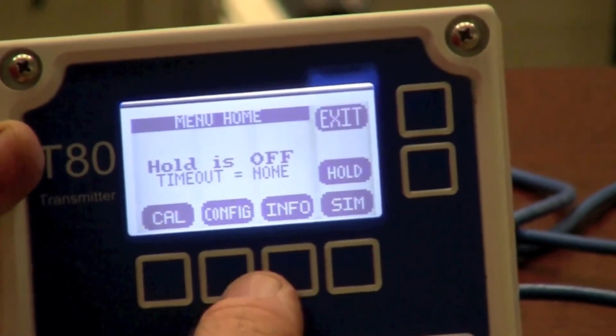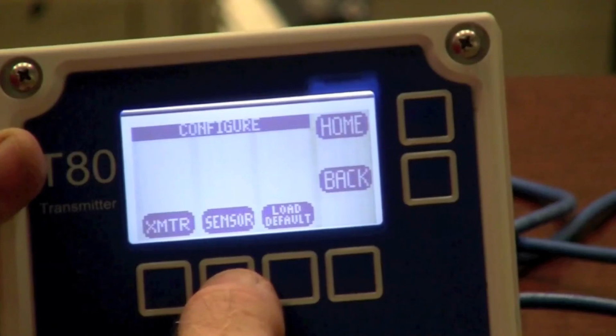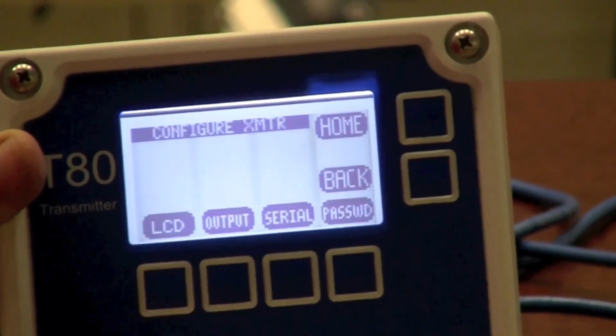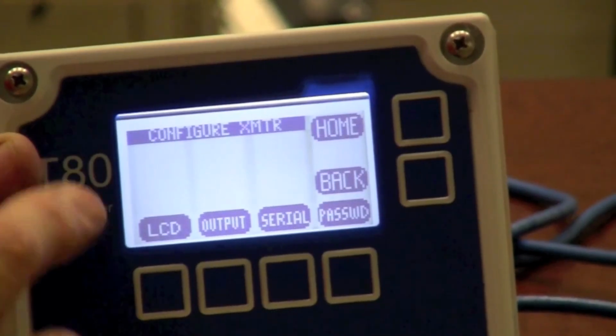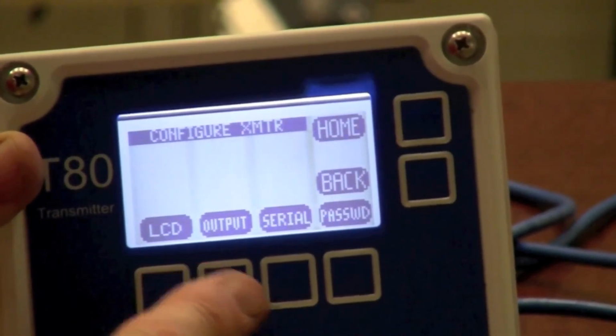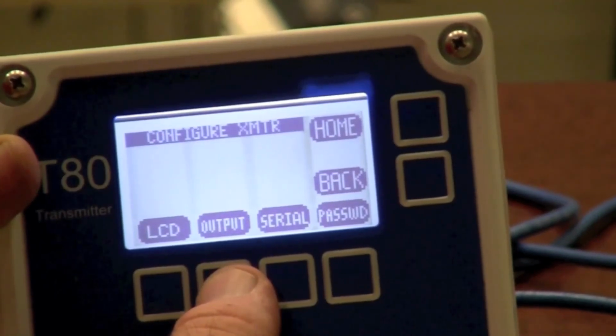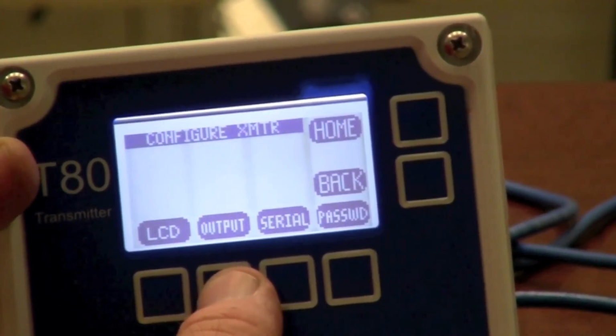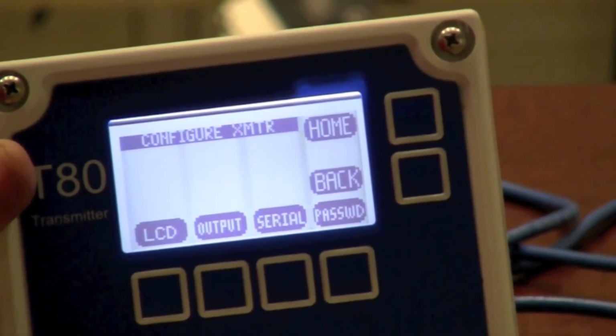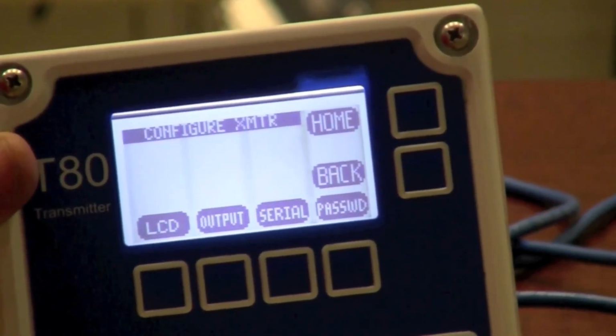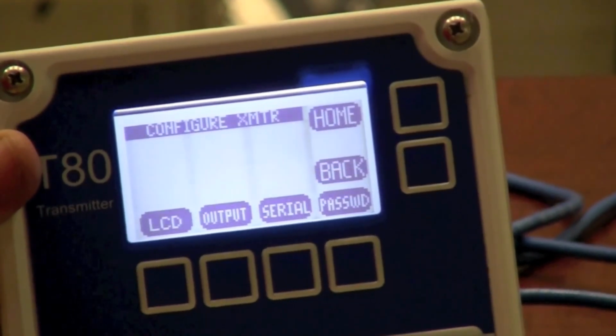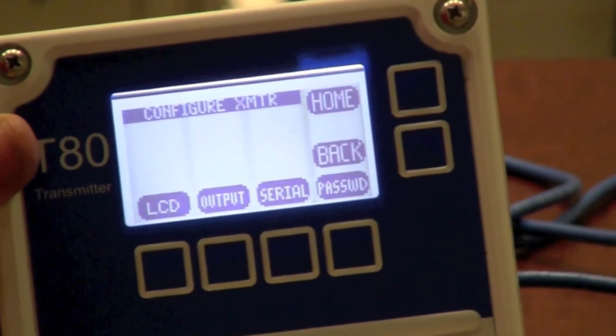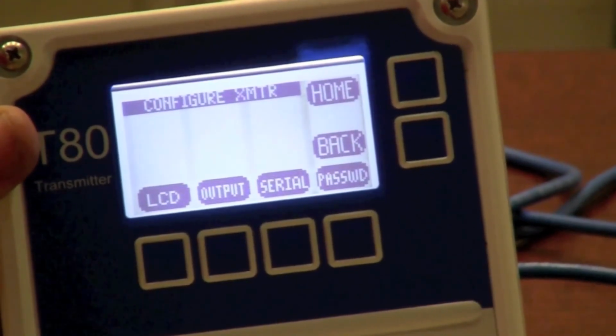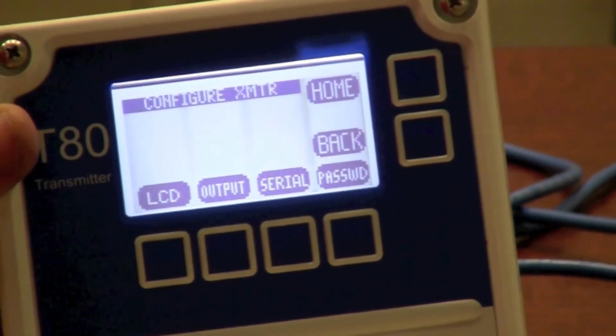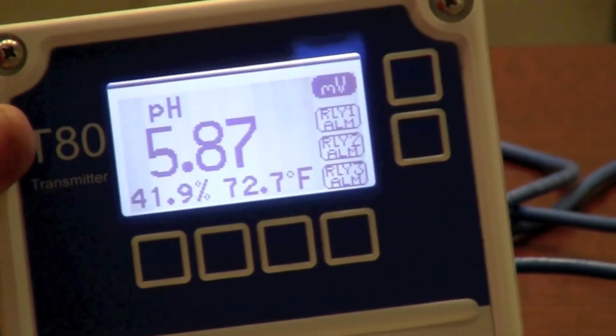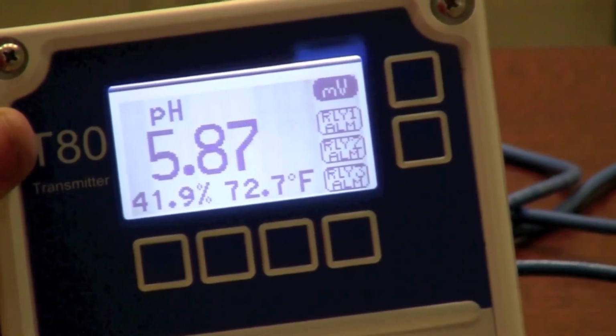Another nice feature is the ability of configuring the transmitter. I can adjust the LCD display. I can adjust the output so that I get the 4 to 20 over the desired range. I can also adjust the serial settings. This unit has a 4 to 20 milliamp output as standard. It has a second 4 to 20 milliamp output as an option. That second 4 to 20 milliamp can be assigned to temperature if a single probe is used. This unit is also available in a dual channel.